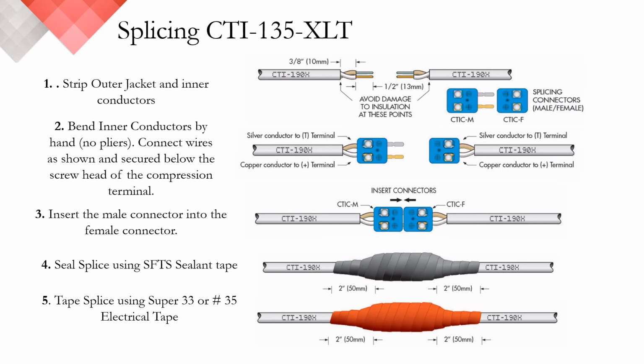Our CTIC splicing connectors are T-type thermocouple rated to assure that all connections on the CTI series circuit remain a T-type thermocouple and eliminate the chance for any parasitic junctions. Standard Euro-style compression terminals used in the PHSC, or were shown in the slide previously, cannot be used with our CTI technology. Once the CTIC compression terminals have been fitted into the detector, the male and female ends are then brought together. Finally, the last two steps with this are identical to our standard PHSC product, where we use an SFTS sealant tape to protect it from the environment, and we cover that SFTS tape in an appropriately rated electrical tape.